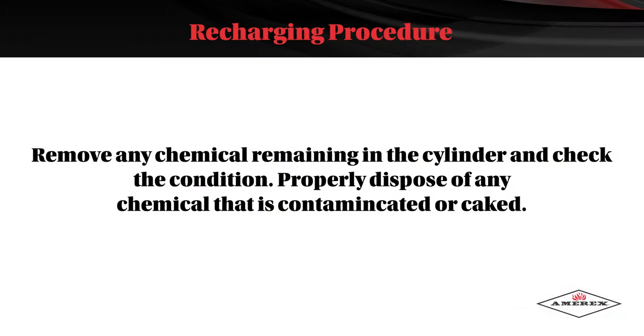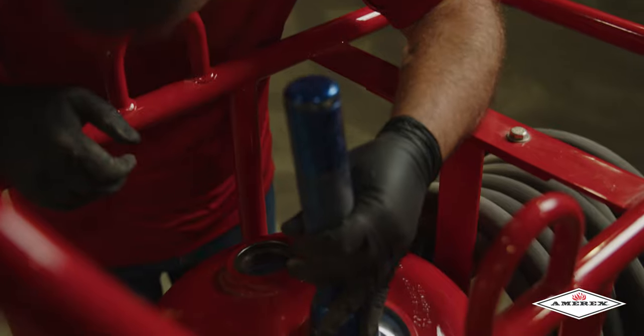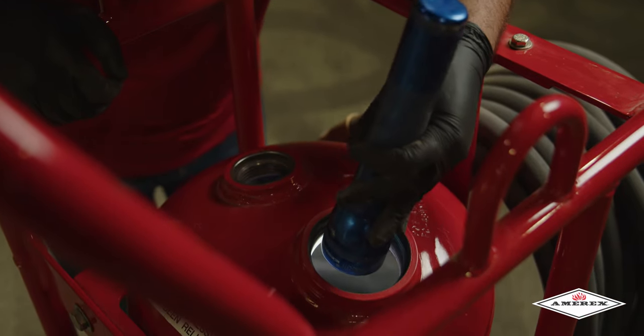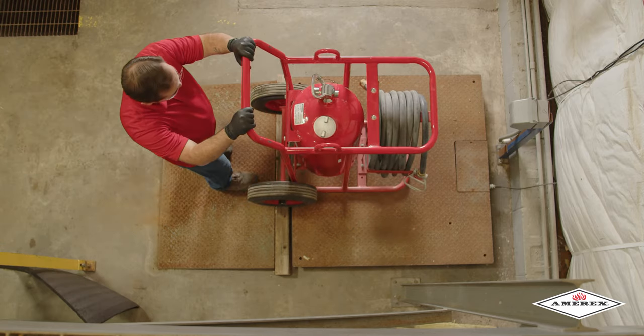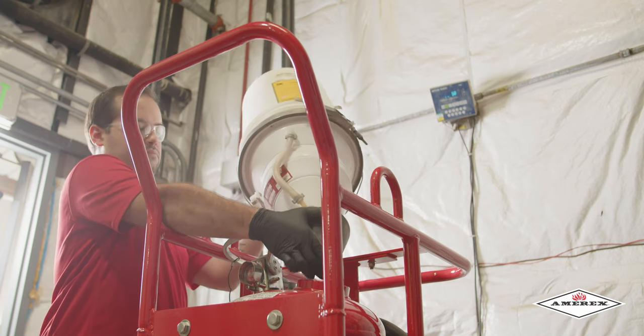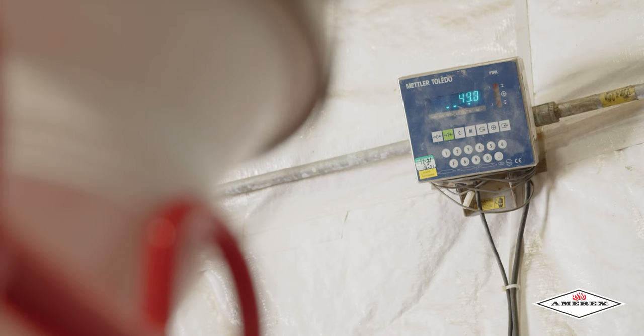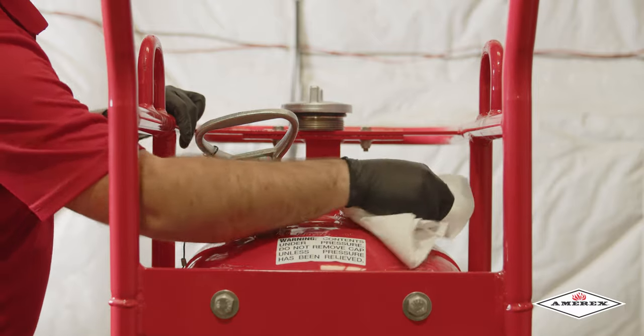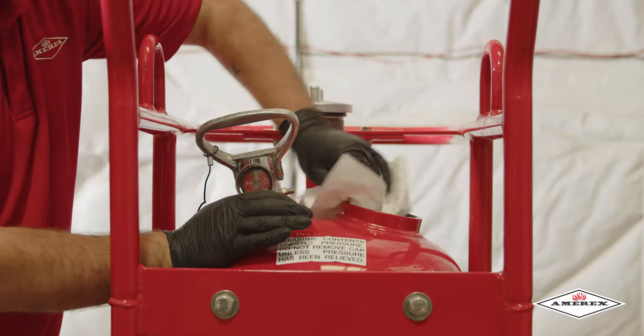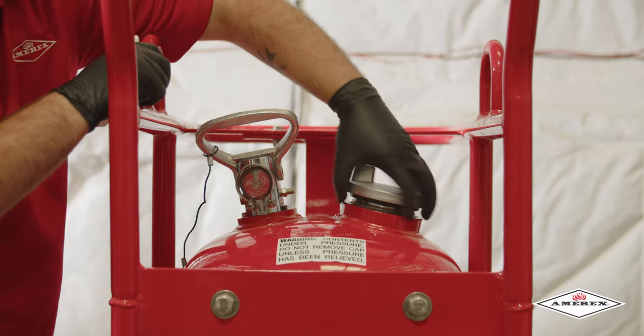Remove any chemical remaining in the cylinder and check its condition. Properly dispose of any chemical that is contaminated or caked. Inspect the cylinder interior following CGA Visual Inspection Standard C6. Using an accurate scale, fill the cylinder with the correct amount and type of dry chemical specified on the label. Use Amerex chemical which has been kept free of moisture and contamination. Do not mix types of chemicals. Clean the cylinder collar O-ring seat and collar threads with a small brush and wipe surfaces with a clean cloth to remove dust. Lightly brush the collar O-ring seat with an Amerex approved lubricant.